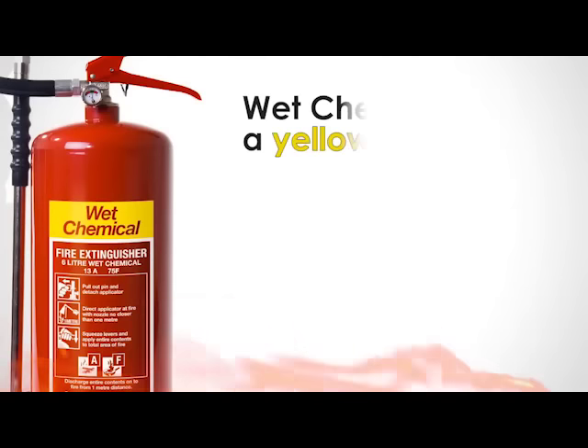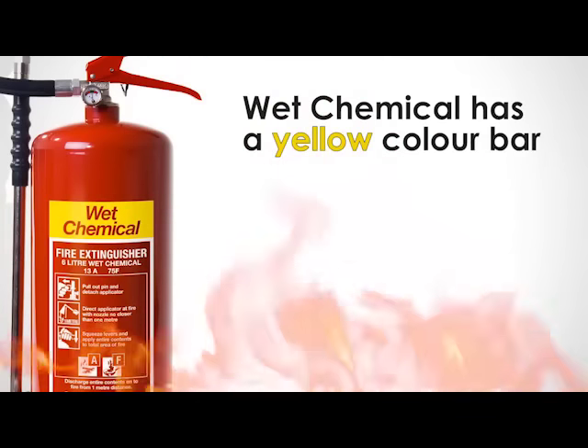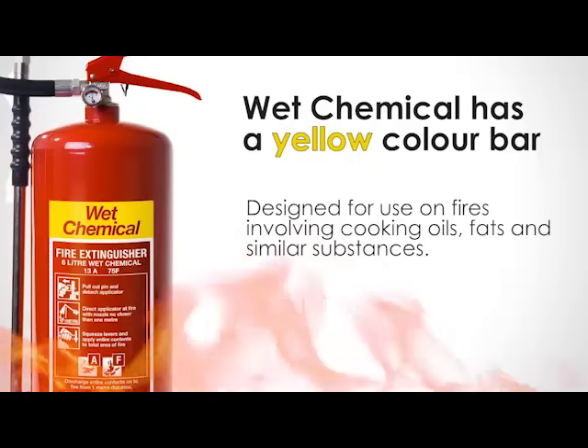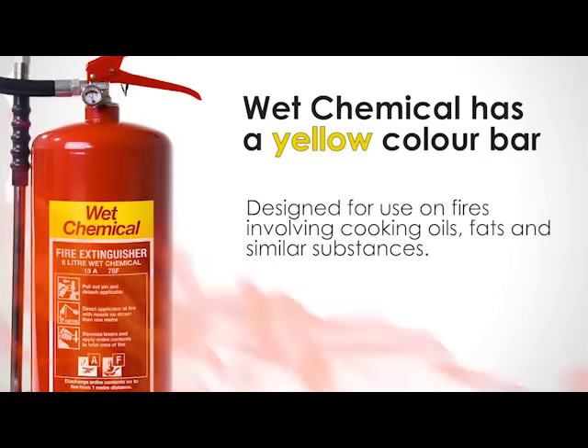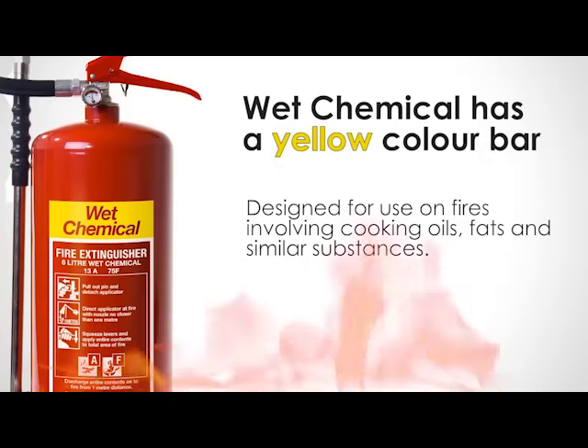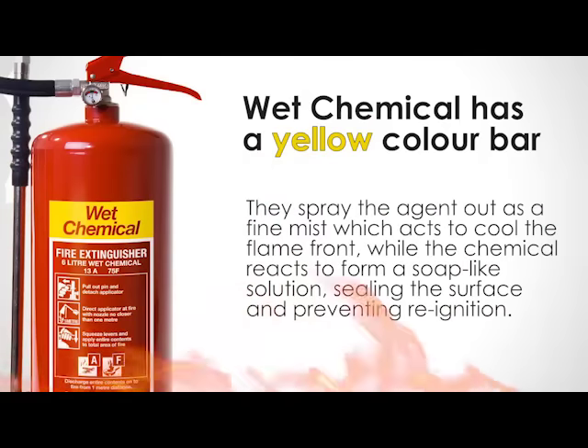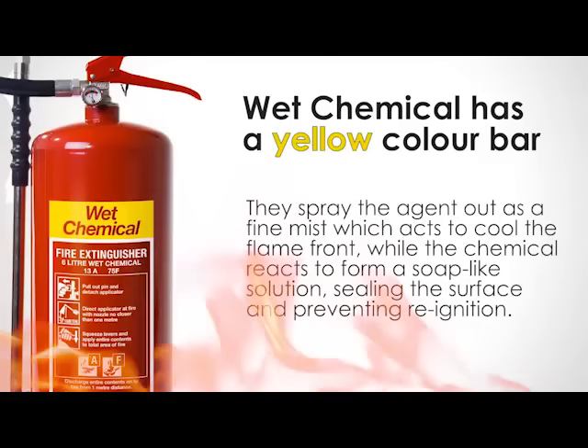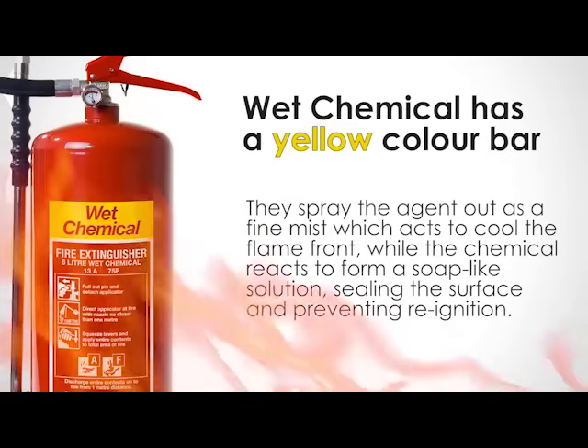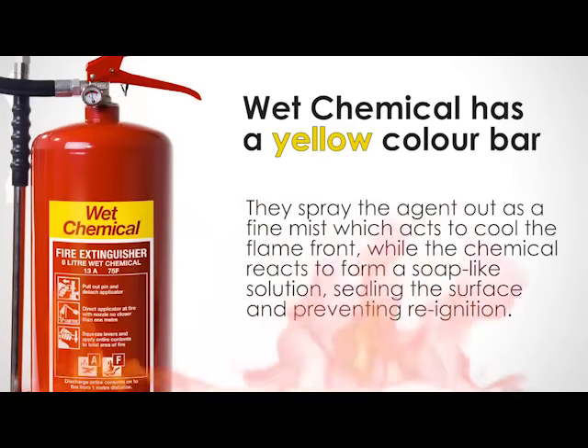And finally, wet chemical. This has a yellow colour bar. These extinguishers are designed for use on fires involving cooking oils, fats and similar substances. They spray the agent out as a fine mist which acts to cool the flame front, while the chemical reacts to form a soap-like solution, sealing the surface and preventing reignition. This provides a similar blanketing effect to the foam extinguisher, but with a greater cooling effect.